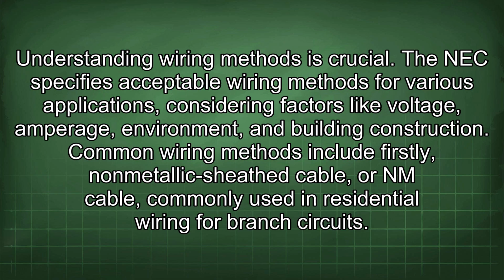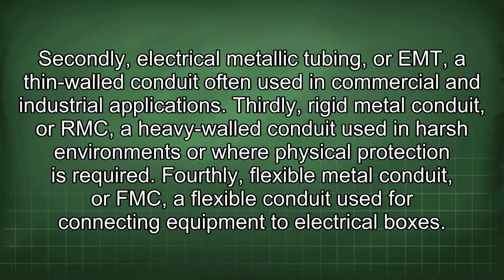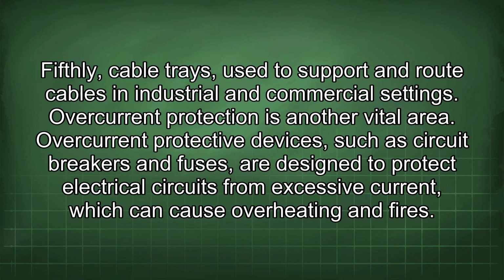Understanding wiring methods is crucial. The NEC specifies acceptable wiring methods for various applications, considering factors like voltage, amperage, environment, and building construction. Common wiring methods include, firstly, non-metallic sheathed cable, or NM cable, commonly used in residential wiring for branch circuits. Secondly, electrical metallic tubing, or EMT, a thin-walled conduit often used in commercial and industrial applications. Thirdly, rigid metal conduit, or RMC, a heavy-walled conduit used in harsh environments or where physical protection is required. Fourthly, flexible metal conduit, or FMC, a flexible conduit used for connecting equipment to electrical boxes. Fifthly, cable trays, used to support and route cables in industrial and commercial settings.